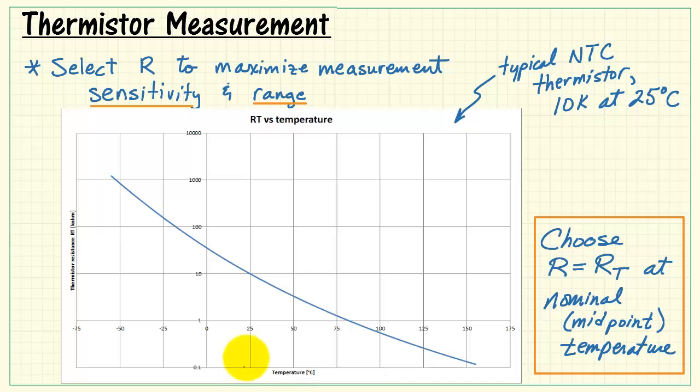Now supposing, in a different application, you're working on the inside of a freezer, for example. So we'd say, in this case, the nominal temperature is 0 degrees C. As we project up, we see that the thermistor has a resistance of approximately 40k.